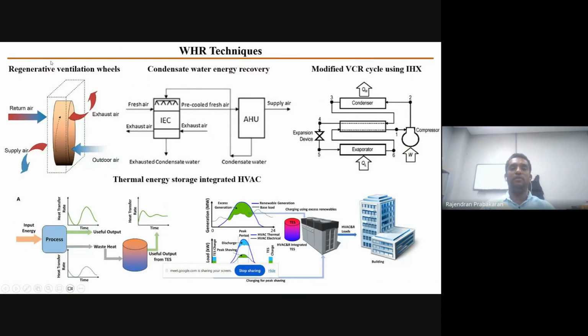In the first one, regenerative, usually what we do is use the return air from the room to pre-cool the supply air. For example, if the return air is at 27 degrees Celsius but the ambient is 32 degrees Celsius, when the 32 degrees Celsius ambient air interacts with the return air, its temperature will be reduced by 2 to 3 degrees Celsius. This helps to reduce the evaporator load and the power consumption.